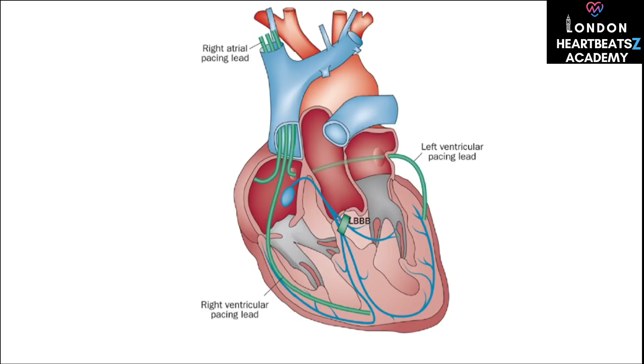But a really crucial test, highlighted in the notes, is testing the LV lead at a high output, like 10 volts. Why so high? To specifically check for that phrenic nerve stimulation, the diaphragm twitching. You want to be absolutely sure it won't happen in any likely device setting. If they detect it, they might have to reposition the lead, even if the location seemed good otherwise. Patient comfort and long-term tolerance are vital. Absolutely. No twitching.